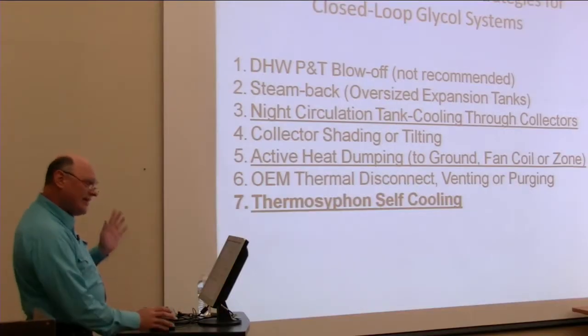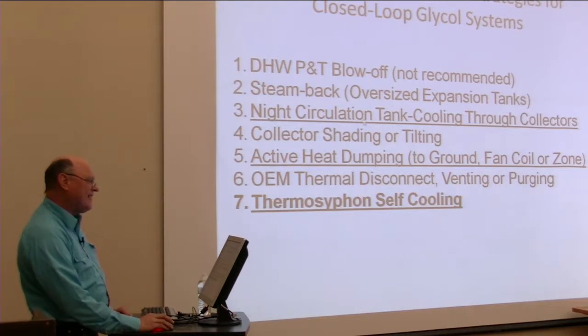But here's a better one, night circulation. You can put all the extra heat into a storage tank, make that tank get really hot but not hot enough to blow off, and then at night, if your controller is intelligent enough to know that the storage tank's hotter than normal, it'll run the collectors and the storage tank pump at night, pulling heat out of the tank, sending it back to the collectors, and radiating it away from the collectors to the night sky. So we're using night sky radiant cooling to cool an overheated tank, under control so nothing bad ever happens. No steam is ever generated. No blow-off valves ever blow off. So that's good. That's built into our controller. You can use that if you want it.